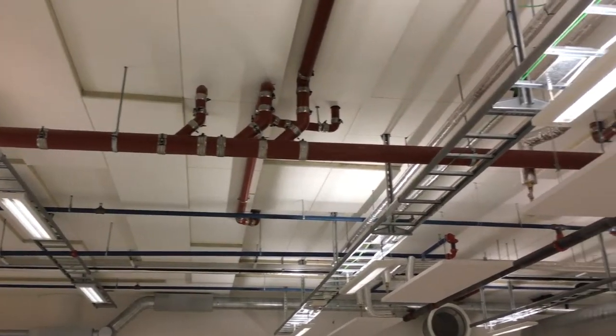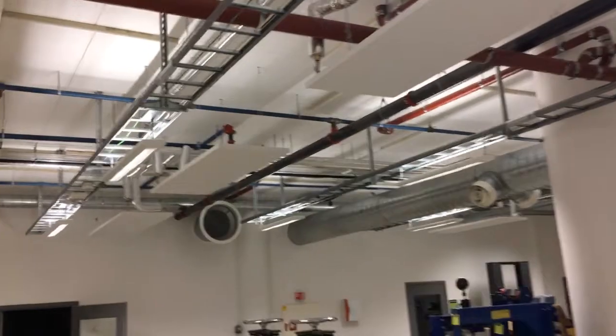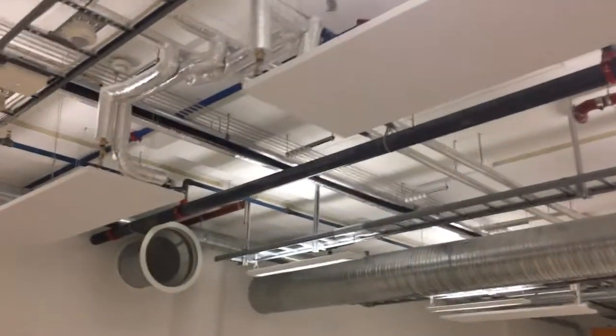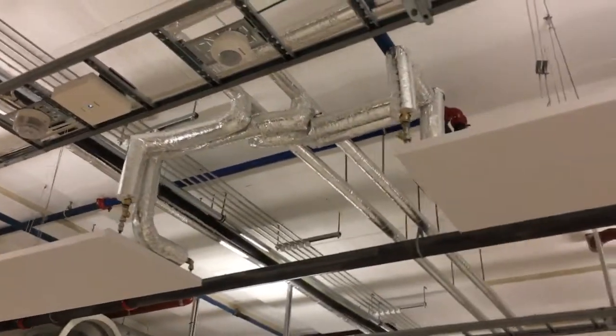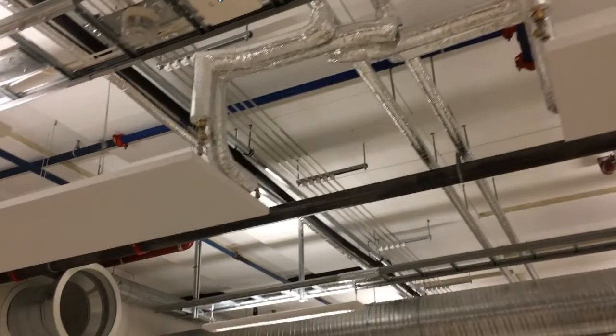As we look over you see another piping system that's interesting. Here we have heaters for this room, and much of the heating in Trondheim comes from a garbage incinerator which produces hot water, and that hot water is circulated in a district heating system. You can see here these insulated pipes are carrying the hot water to these radiators, and they're insulated to keep the heat in so that we're not losing it on the piping system but rather being passed to the room through these radiator systems which are in every room in this building.